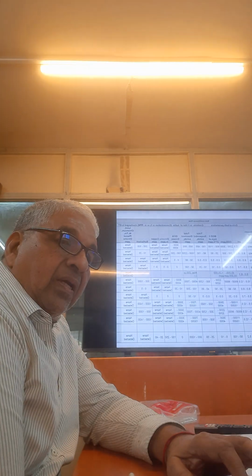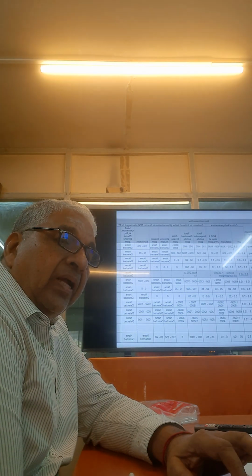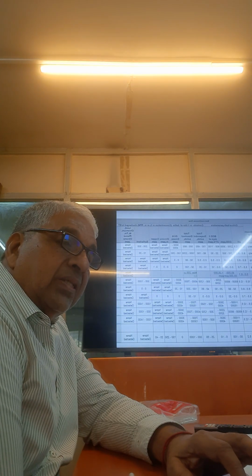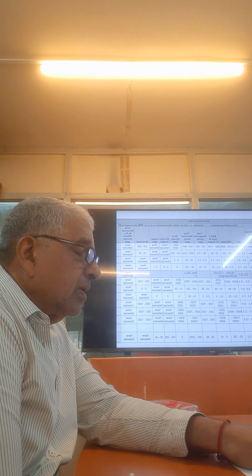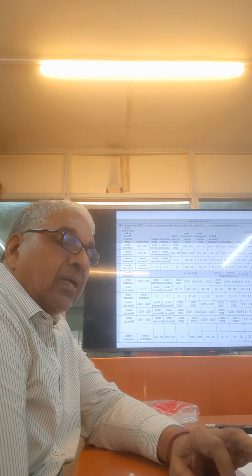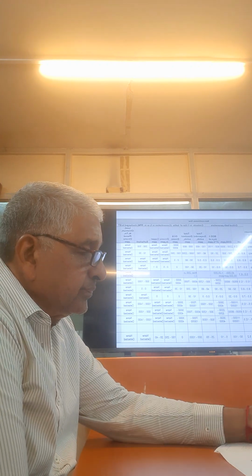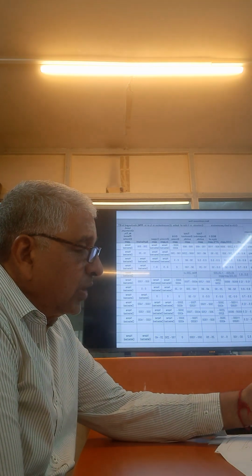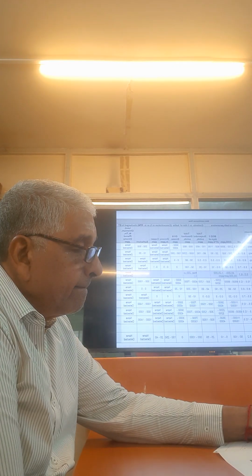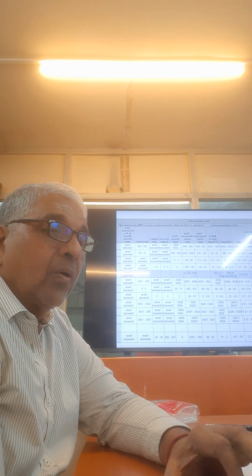Maybe I will make it 50, taking into account this 42 KL. Only based on this we have given 38 KL as ETP3 high TDS 1. I will make it 50 so that one dump can be fully handled. And this happens once in a quarter.